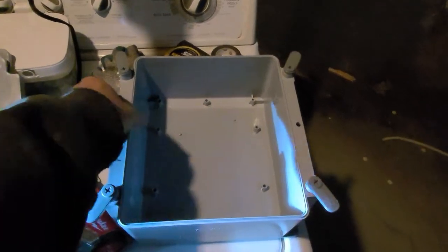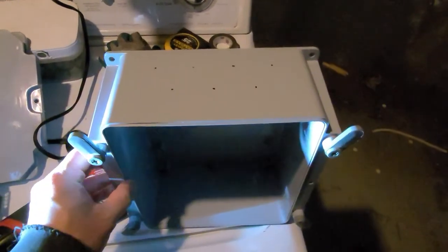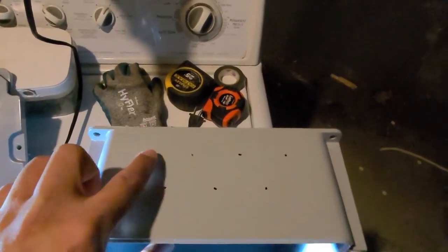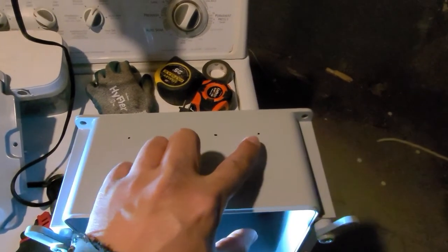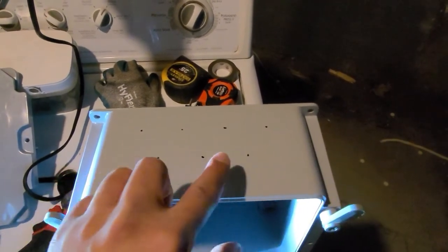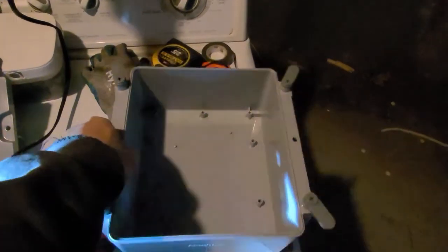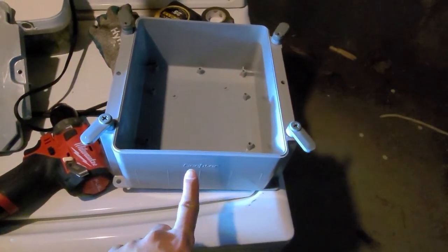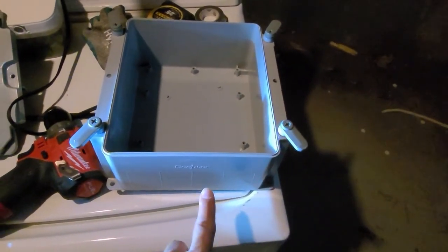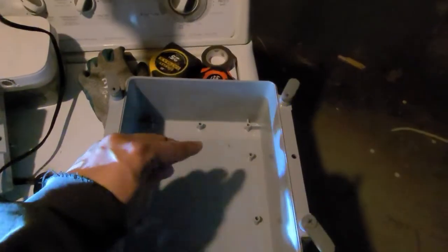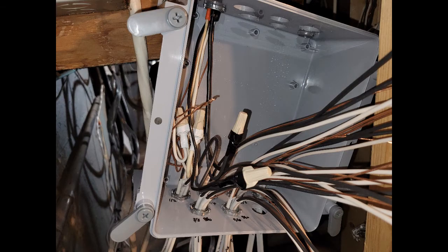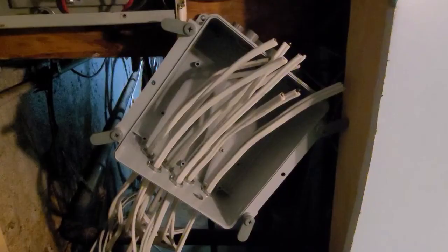So when we swap to the new electrical panel, for those wires which are long enough, we simply terminate the wire into the new panel. But for those wires which are too short, we need to put a junction box in between the older wire and the new wire that goes to the electrical panel. So we have to refer back to the electrical code to find the proper size of the junction box, not only to meet the code requirement, but also make our work easier.